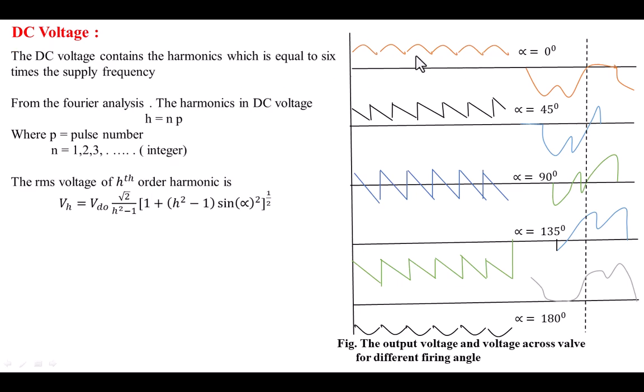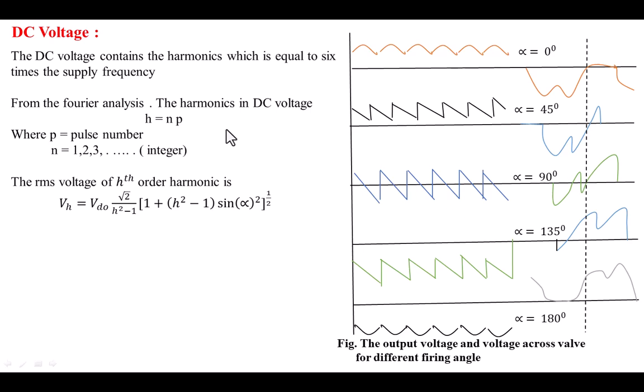The harmonic order in the output DC voltage is equal to H = N × P, where N is an integer changing from 1, 2, 3, and P is the pulse number. For this 6-pulse converter, P = 6. The RMS voltage of the Hth order harmonic is VH = VD0 · √2 / (H² − 1) · √(1 + (H² − 1)·sin²α). If we take N = 1, the first harmonic order is 6. If N = 2, the harmonic order is 12. Continuing: 6, 12, 18, 24 — these are the harmonics present in the output voltage.